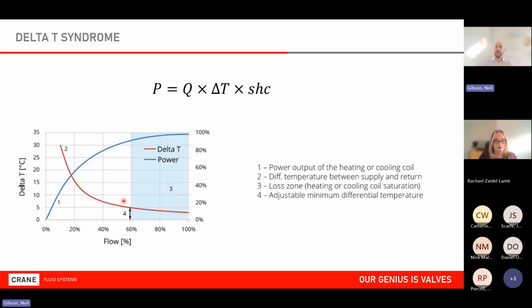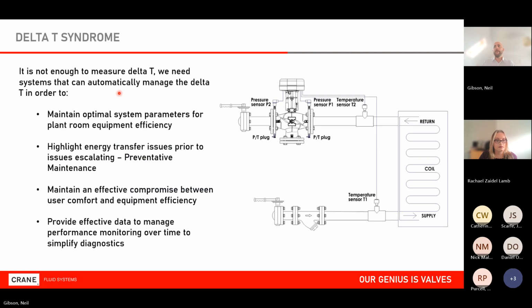So how do I prevent myself getting into this zone? What we traditionally have are systems which can do it with heat meters, etc. We can do it with temperature sensors. We have systems that can monitor it, and that's about as good as we do usually. So we monitor the situation, and then we eventually get a report that tells us delta T is poor or power output is compromised, whatever the reason. And what we're saying is that that's not good enough. What we need is a system that can not only monitor the temperature, monitor the delta T, and monitor the power, but correct itself when it sees things aren't going right, and can maintain a value to protect the efficiency of the plant room.